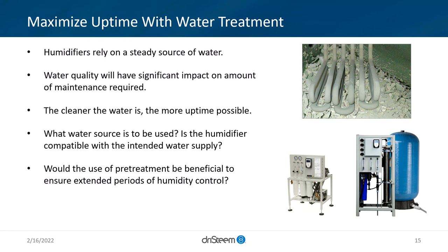And water treatment, specifically reverse osmosis, removes 98% of that total dissolved solids. And even one step further, deionization of that water removes that last 2% that the RO cannot remove on its own, just through its own process design.